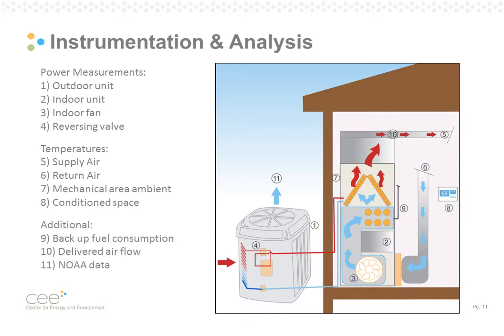We've got thermocouples measuring the supply and return air temperatures. We're also measuring the temperature of the mechanical area and collecting temperature data for the conditioned space. Additionally, we've got a gas meter to measure the backup fuel consumption for the furnace. We've taken delivered airflow measurements using a TrueFlow, and we're also collecting NOAA data from the closest weather stations to each of these homes.